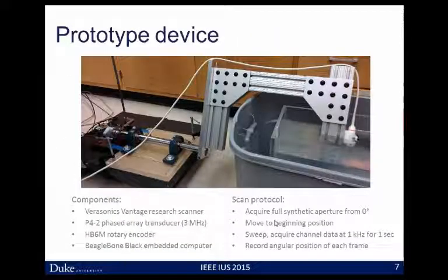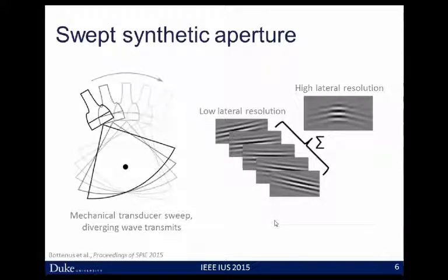The basis of this technique is a mechanical transducer sweep. We sweep in an arc from left to right, and as we do so, we precisely track the location of that transducer. As we sweep, we transmit diverging waves covering the region of interest in the center. You can use other virtual source or plane wave techniques as long as you sufficiently insonify the region of interest. At each position we acquire a low-lateral-resolution image. Here we see five samples, each of which has already been spatially registered using that known position information. That sub-wavelength positioning allows us to coherently sum this RF data and build up a single high-lateral-resolution image.